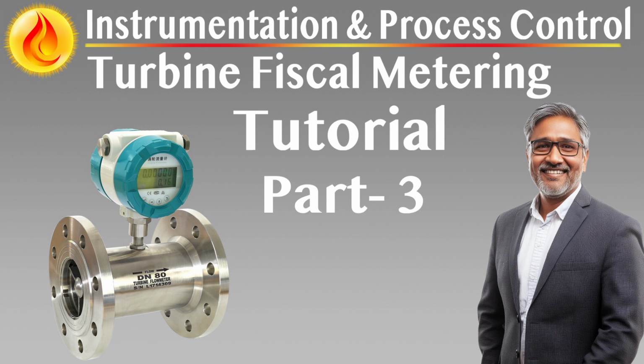Control valves must be capable of modulating smoothly from minimum to maximum flow without introducing hydraulic shocks or oscillations. They must also provide rapid shutoff and fine throttling to support proving sequences and ensure consistent proving volume delivery. The valve actuation mechanism must include position feedback for closed-loop control and be interfaced with the control system for remote set point input and status monitoring.